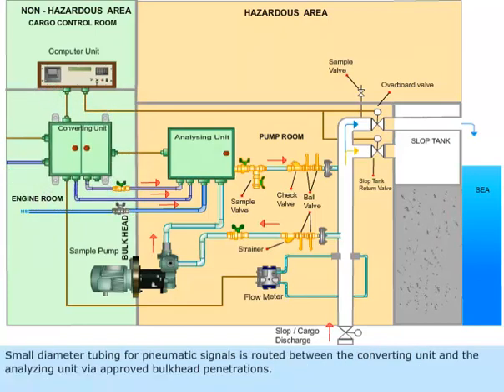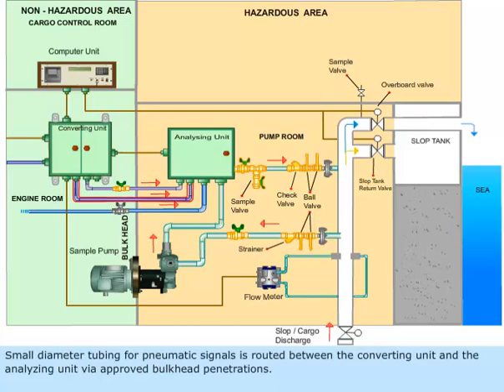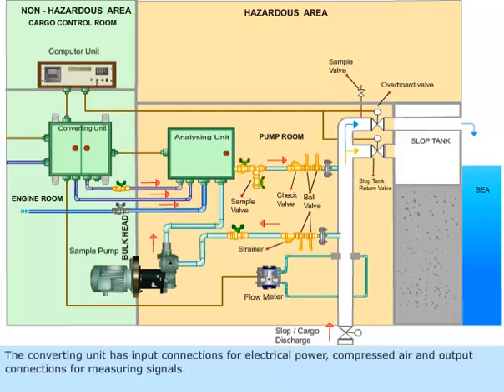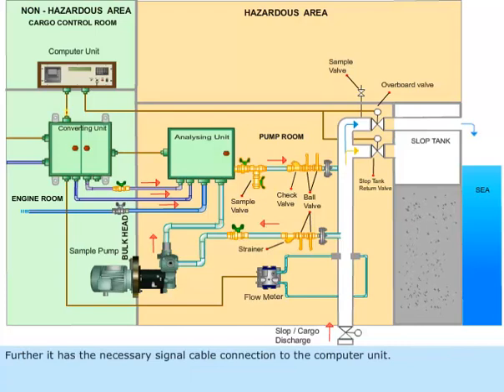Small diameter tubing for pneumatic signals is routed between the converting unit and the analyzing unit via approved bulkhead penetrations. The converting unit has input connections for electrical power, compressed air and output connections for measuring signals. It also has the necessary signal cable connection to the computer unit.